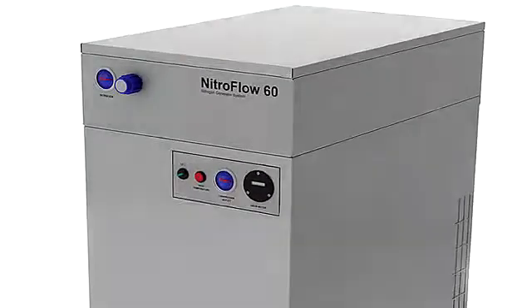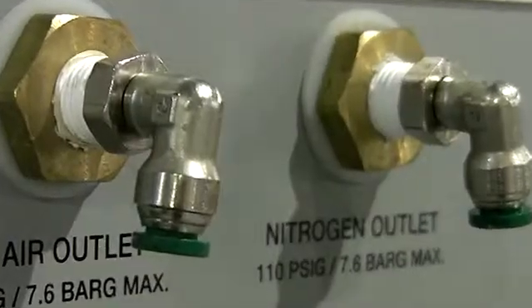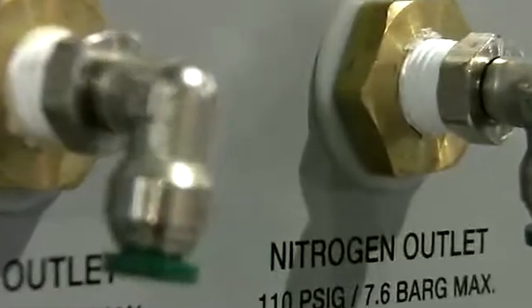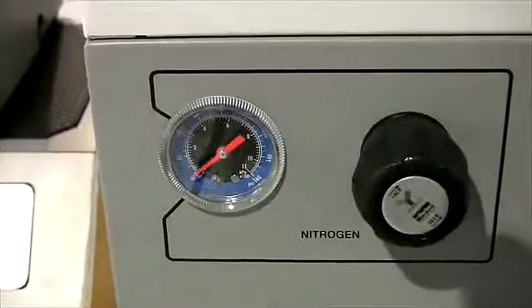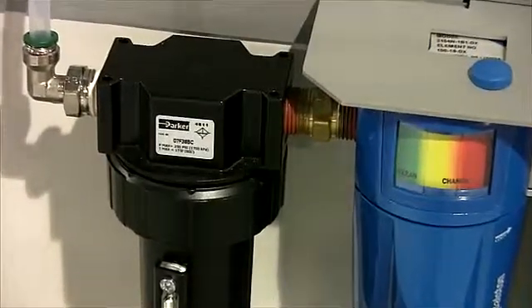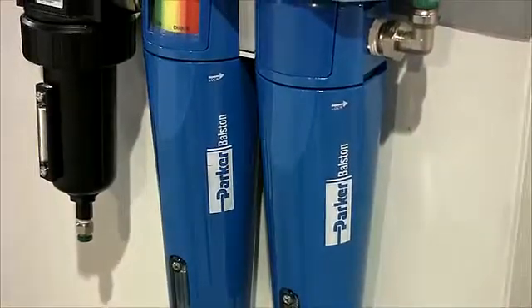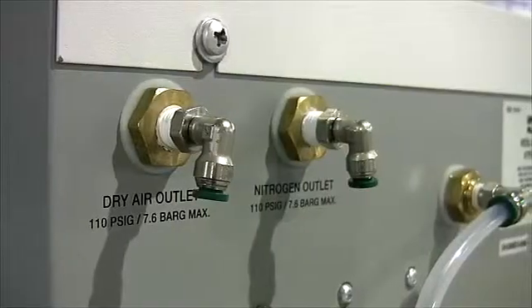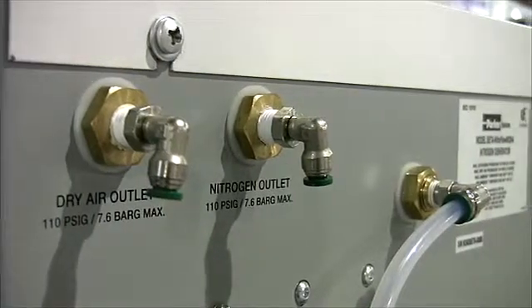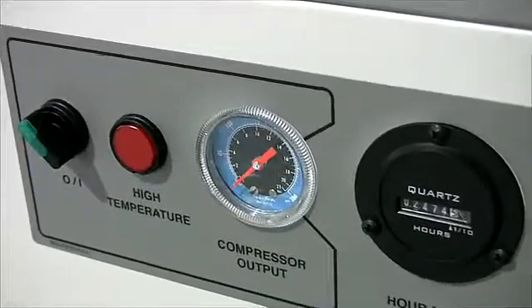The NitroFlow 60 Nitrogen Generator from Parker Balston is ideal for today's higher flow ultra-sensitive LC-MS instruments. Producing up to 60 litres per minute of LC-MS grade nitrogen at pressures up to 110 PSIG, the flow output of the NitroFlow 60 is the equivalent of using one cylinder of compressed gas every two hours, and eliminates any associated safety concerns, costs, and the inconvenience of using cylinders.